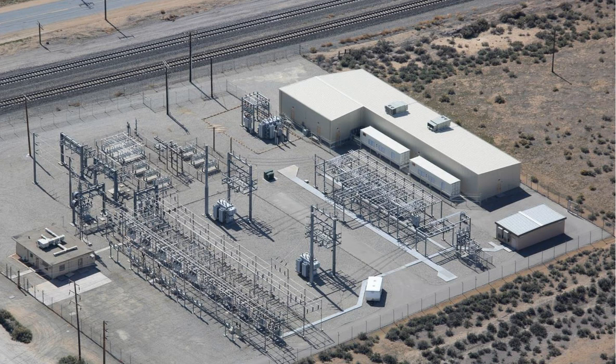The original mini system provided engineers with support for full system startup and commissioning, but with only one battery section and one inverter lineup, engineers were unable to test the multi-inverter lineup battery section operation of the system in the laboratory, such as intersection balancing controls, multi-inverter operation, and symmetrical and unsymmetrical operation of the inverter lineups. To more closely resemble the full system, the mini system was expanded in December 2015 to include twice the number of each component, resulting in a system with two inverter controllers, inverter lineups, and battery sections.